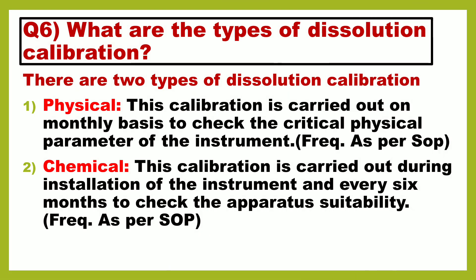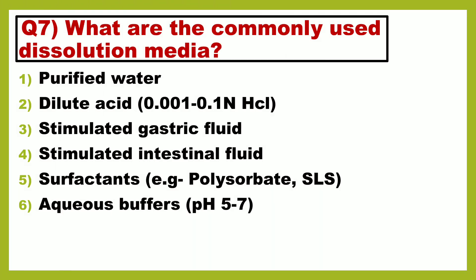Next question is: what are the types of dissolution calibration? There are two types of dissolution calibration. Number 1 is physical calibration — this calibration is carried out on a monthly basis to check the critical physical parameters of the instrument, or as mentioned on the SOP. Number 2 is chemical calibration — this calibration is carried out during installation of the instrument and every 6 months to check the apparatus suitability, or as mentioned on the SOP.